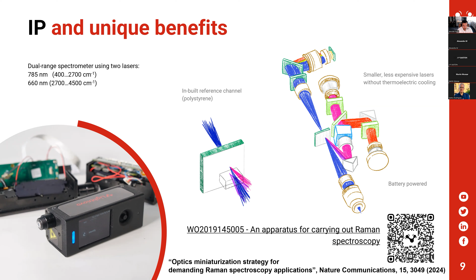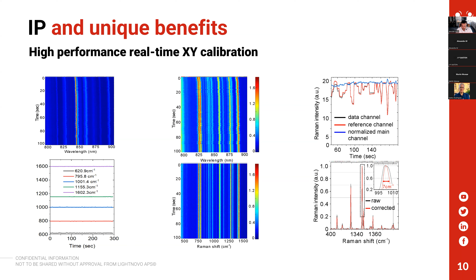The main 785 laser gives the spectral range from 400 to 2700 wave numbers, while an optional 660 nanometer laser gives the spectral range from 2700 to 4500 wave numbers. The X and Y calibration is performed in real time. And as you can see, this allows us to get very stable Raman spectra, even for very unstable lasers.